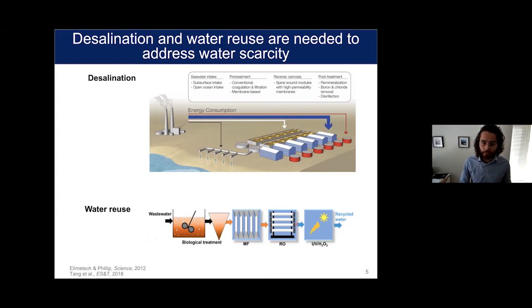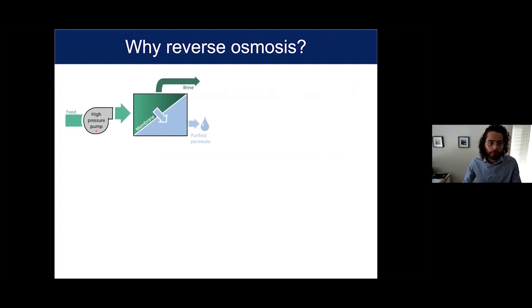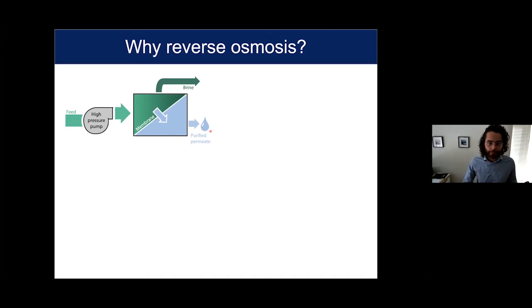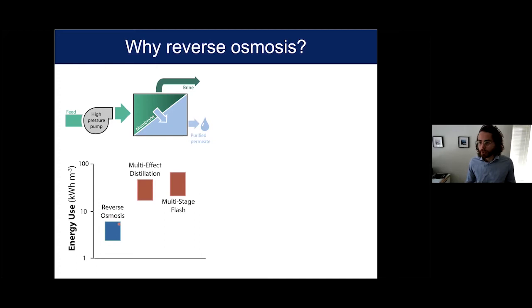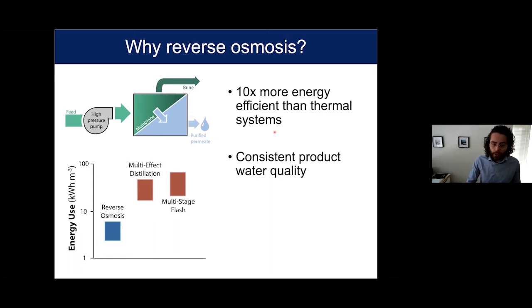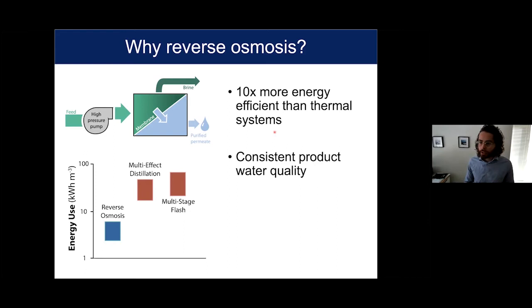Why has reverse osmosis become so dominant in advanced water treatment? Reverse osmosis works by taking feed water, putting it through a high pressure pump, then into a membrane module where water permeates through the membrane while most other things are rejected into a brine stream, leaving purified permeate water. Reverse osmosis is so widely used partly because it's very efficient — this shows the energy use of RO compared to thermal separation processes like multi-effect distillation and multi-stage flash. RO is around an order of magnitude lower in energy consumption and really approaches the thermodynamic minimum.